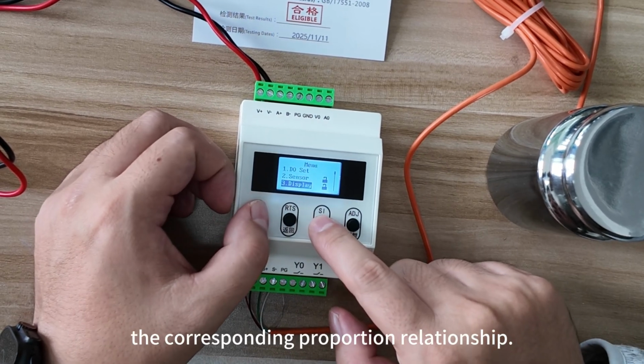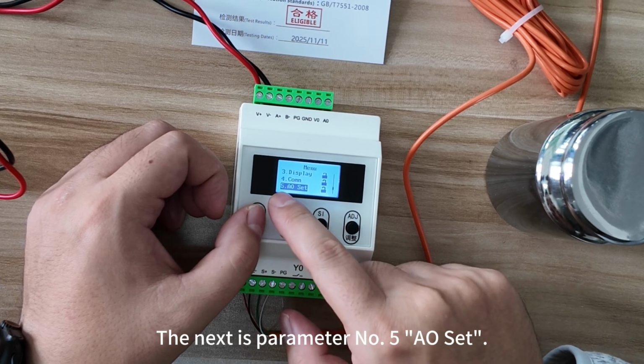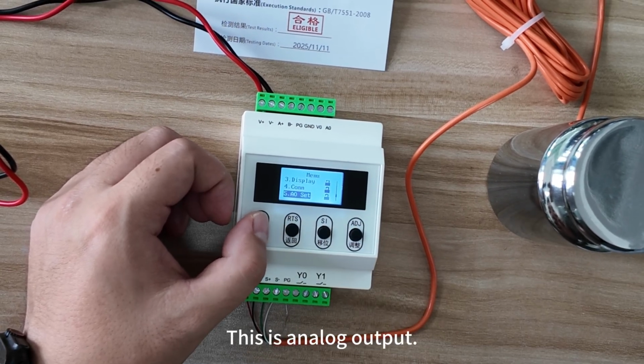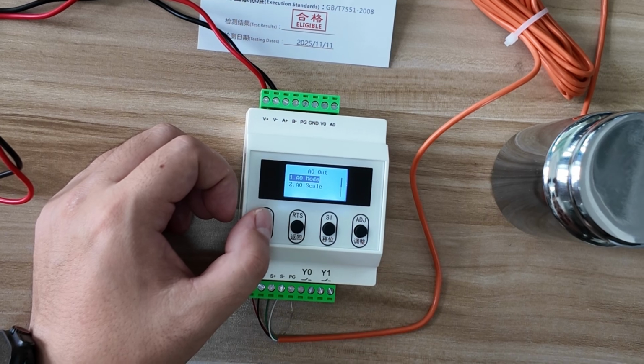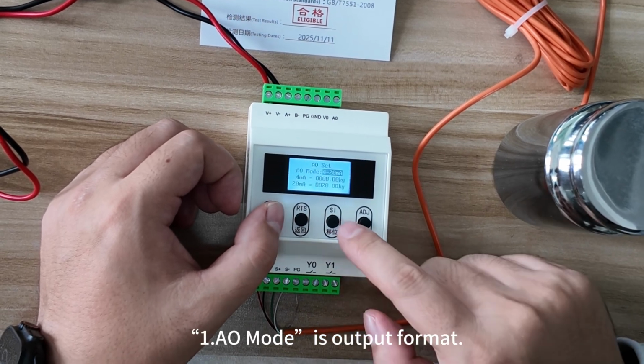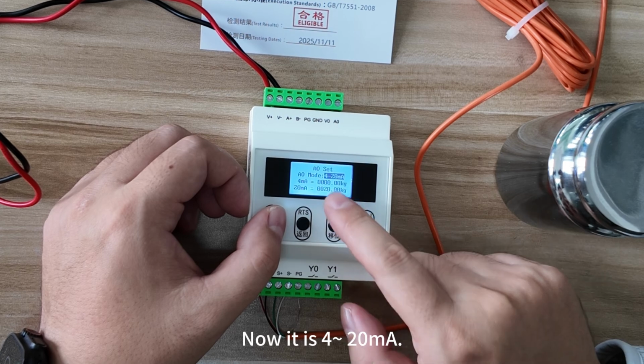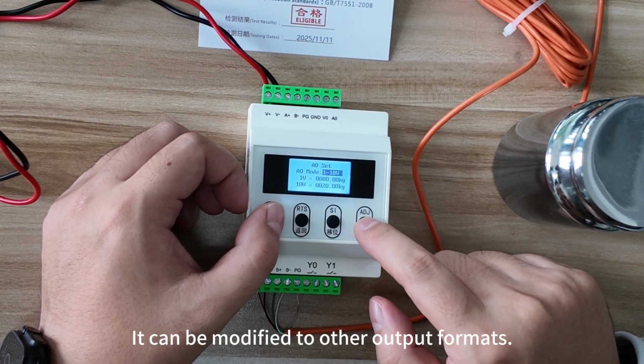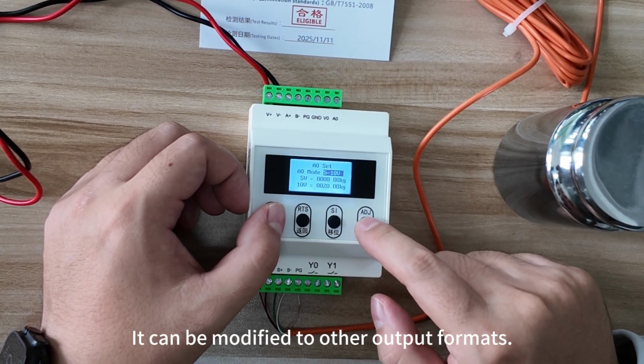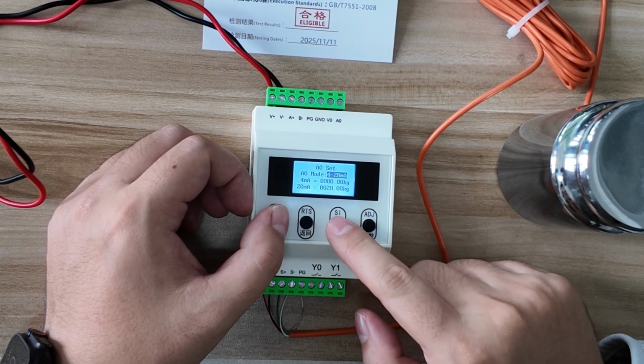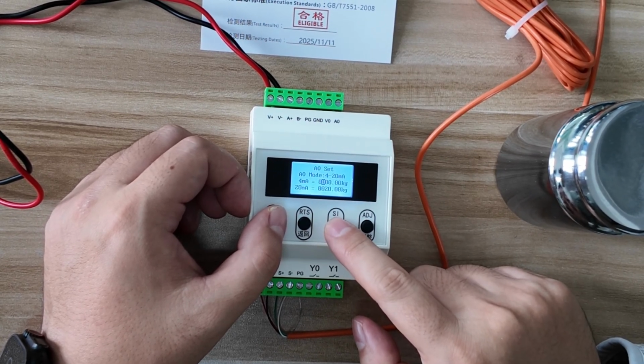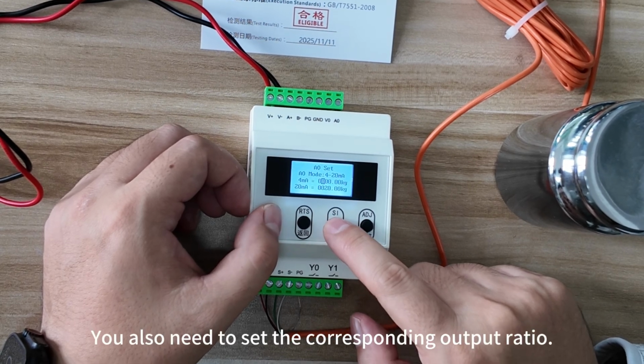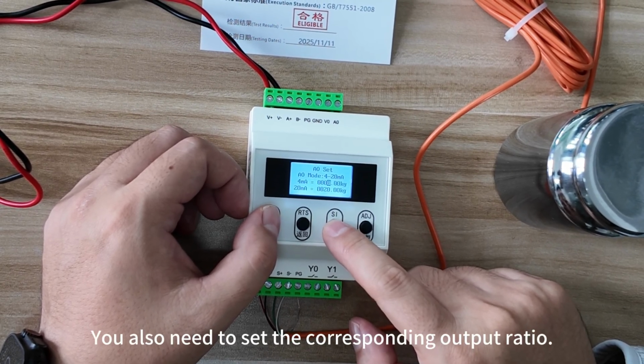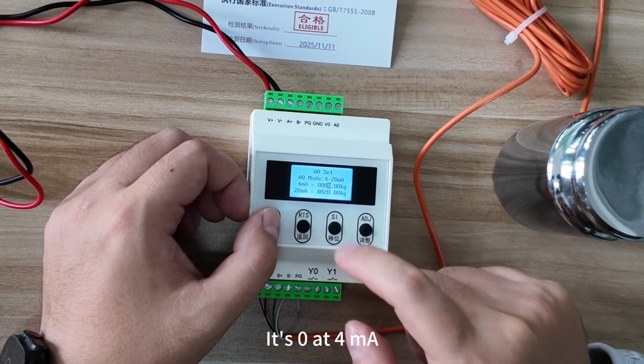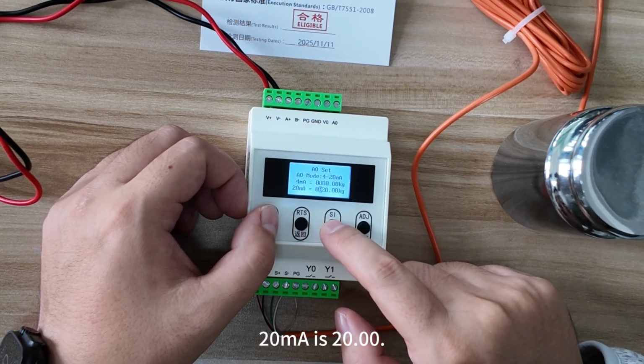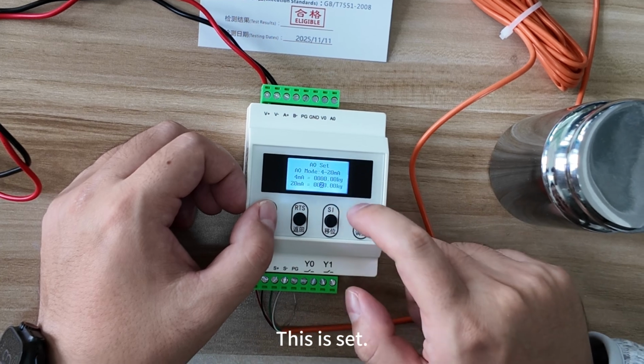The corresponding proportion relationship. The next is parameter number 5, AO set. This is analog output. 1. AO mode is output format. Now it is 4 to 20 milliamperes. It can be modified to other output formats. You also need to set the corresponding output ratio. It's 0 at 4 milliamperes. 20 milliamperes is 20.0. This is set.